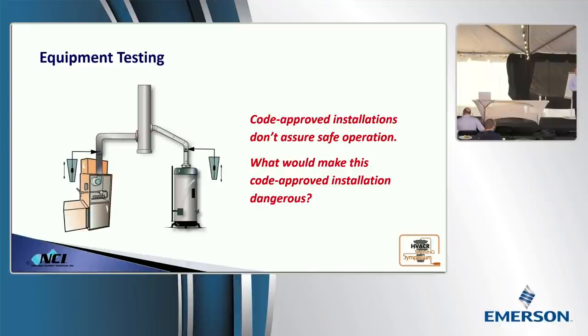You ever see that? Let's talk about what's going on. If you have an occasional pilot outage, the water heater's running. Everything's great. Typically, this will happen early morning. Homeowner gets out of the shower. Like, oh, man, it's cold. Turn the furnace on. Furnace kicks on. What does that inducer do for about 35 to 45 seconds? It purges.